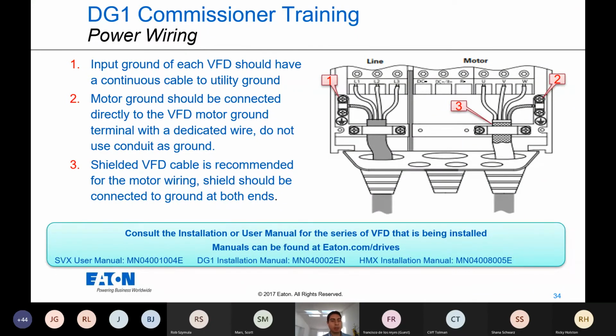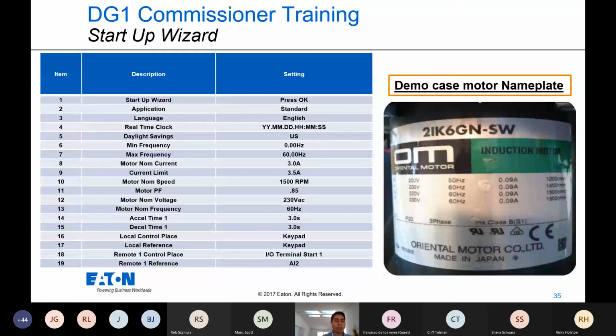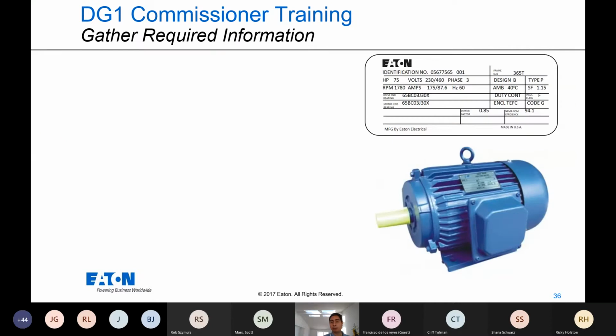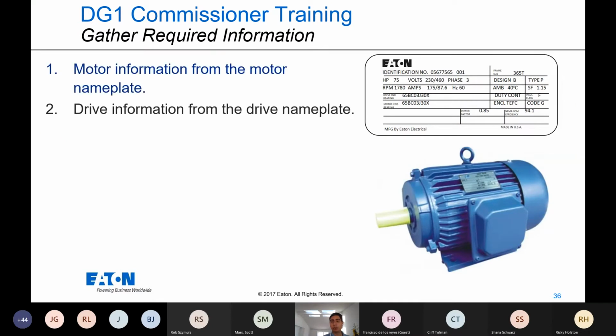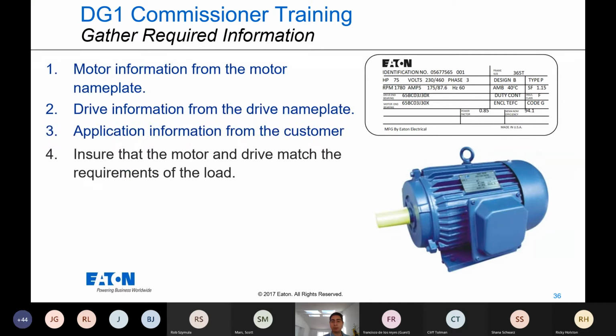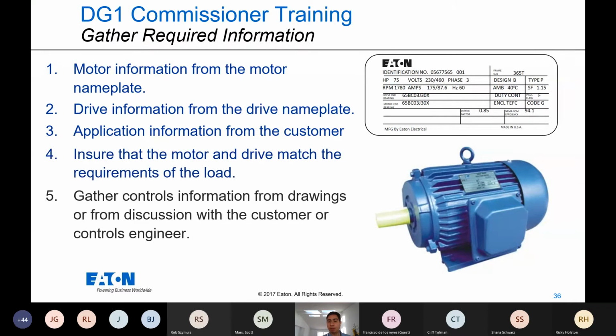longer lasting machines. The basics here is whenever you start a drive, it should have a startup wizard. The startup wizard is a basic 19 parameters, as I show, where you have to pass the motor nameplate data onto your VFD. Most importantly, make sure that your values transcribed here come from the motor nameplate. This is critical. You might see many nameplates on different portions of the system, but make sure that the motor on your pump is the one you're programming into the drive.